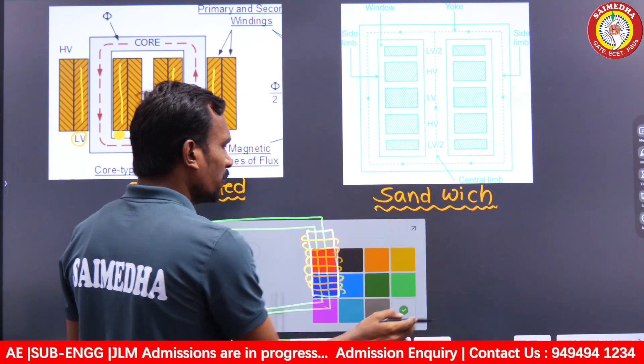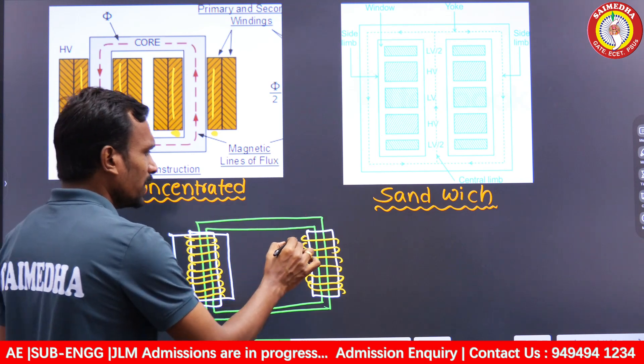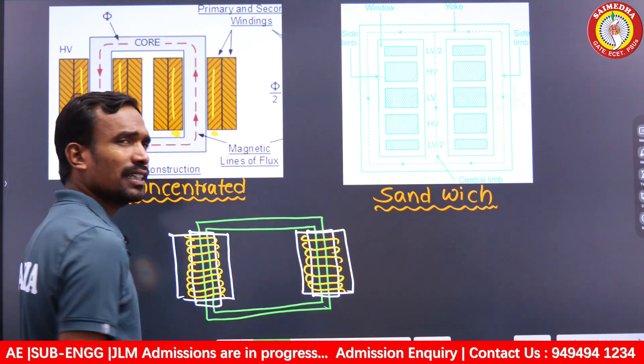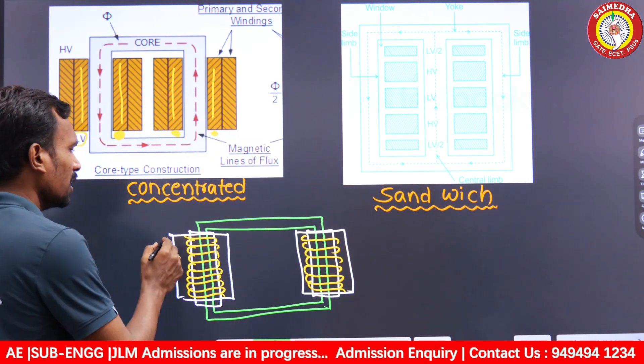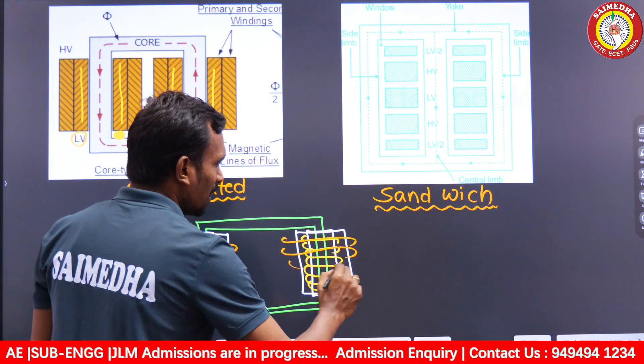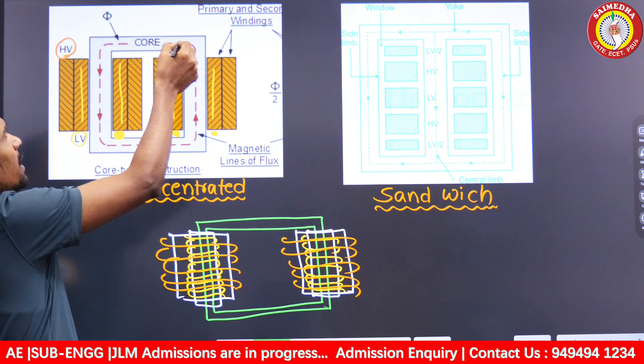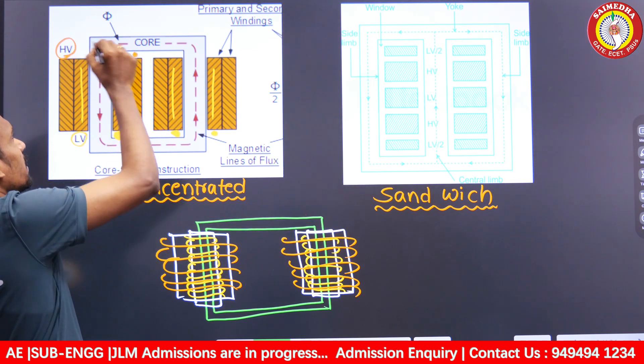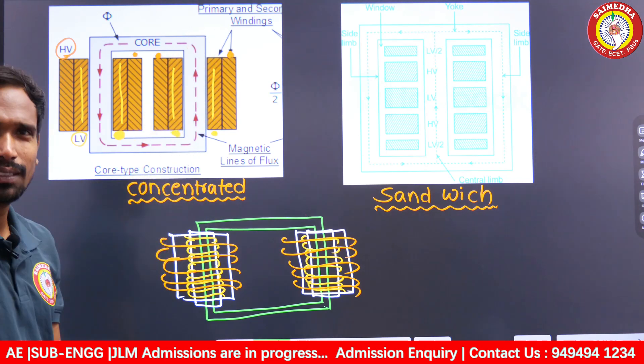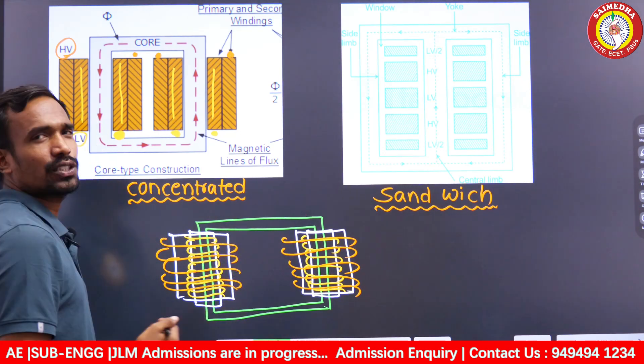On top of the LV winding, we again place insulation. After the insulation, we place the HV winding. So the layering sequence is: first insulation on the core, then LV winding, then insulation again, then HV winding. These are the high voltage windings placed over the insulation layer.